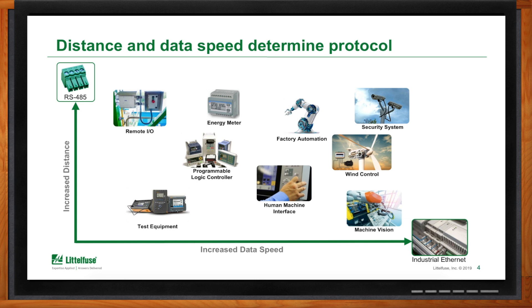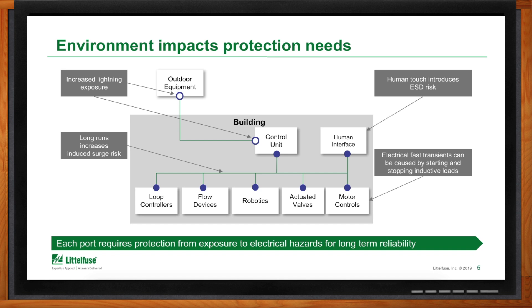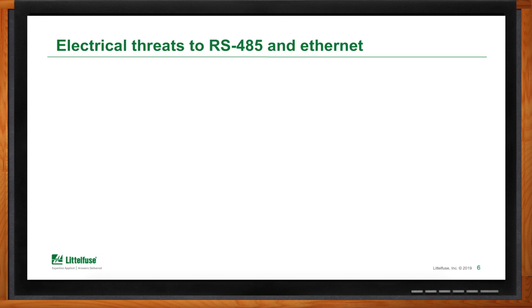Location is critical to port protection. If you have a line outside, you need to be aware of lightning — both where the outdoor port connection is and where it runs inside a building. Long runs require concern about inductive surge risk, and wherever a human may touch something you need to be concerned about electrostatic discharge. Also, wherever motors stop and start, that can cause electrical fast transients.